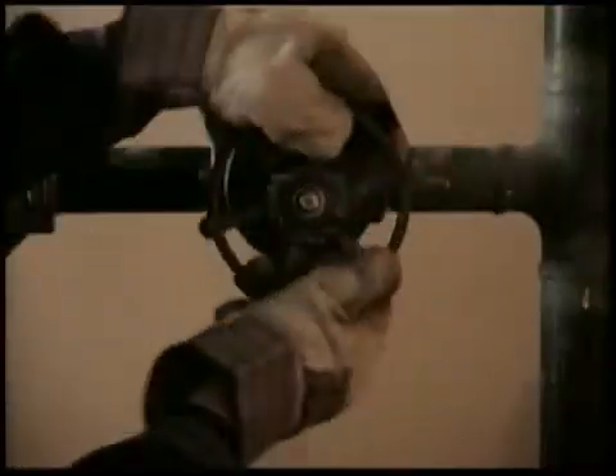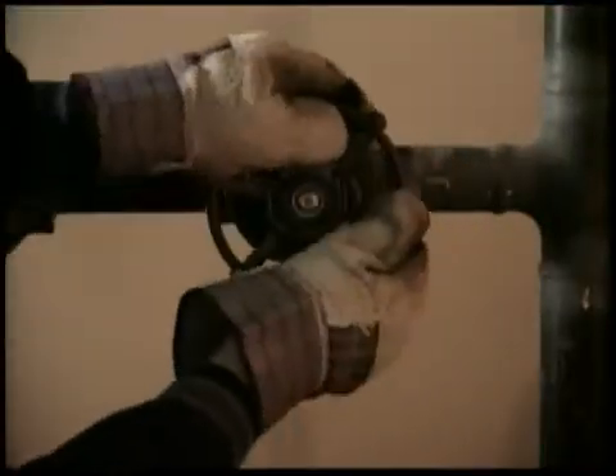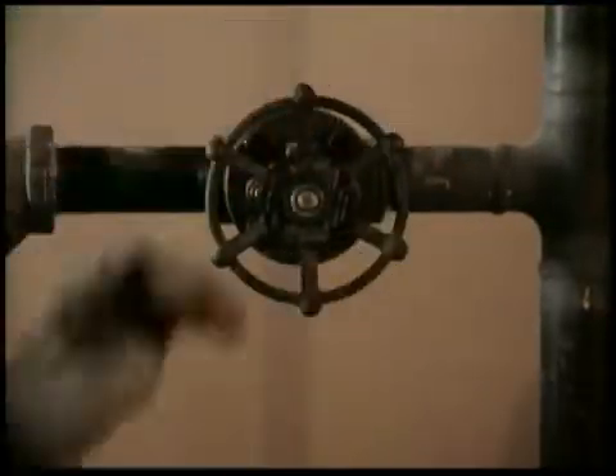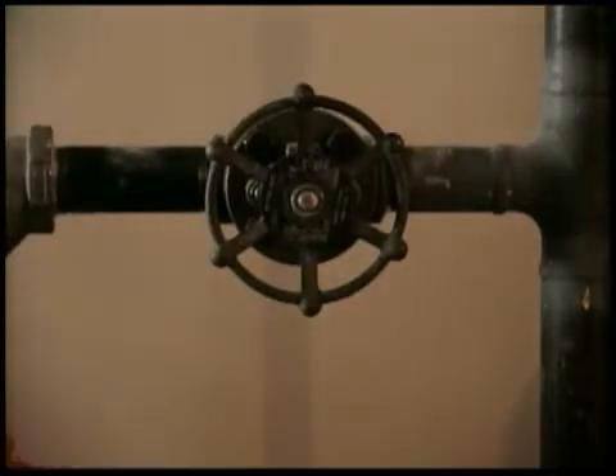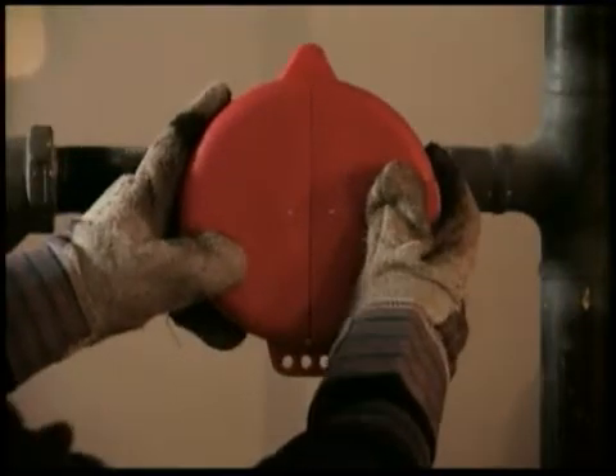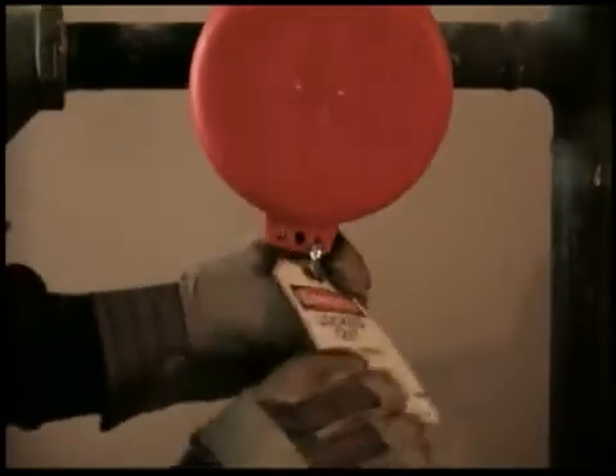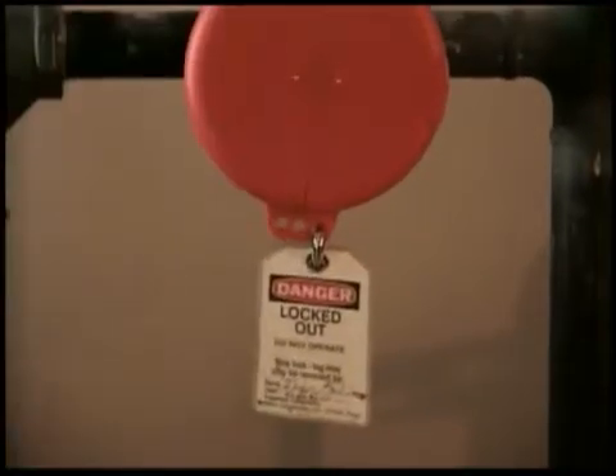Lockout Tagout should also be used to control stored thermal energy hazards, like working on a steam line. If you have to break into a line, shut off the valve and make sure it stays off while you're working by using a valve lockout device like this one. It fits over the entire valve, and when a lock is attached, the valve can't be turned. Carefully release the stored energy in the line, and you're ready to start work.